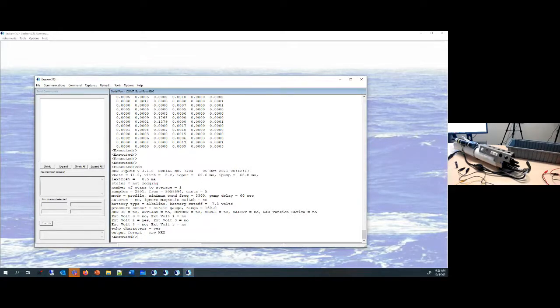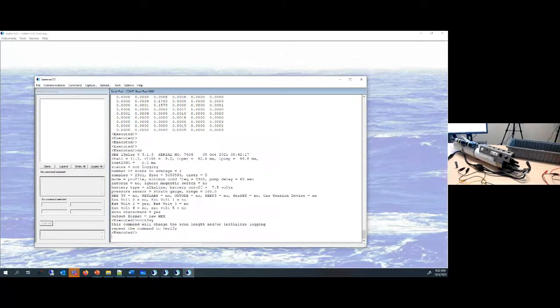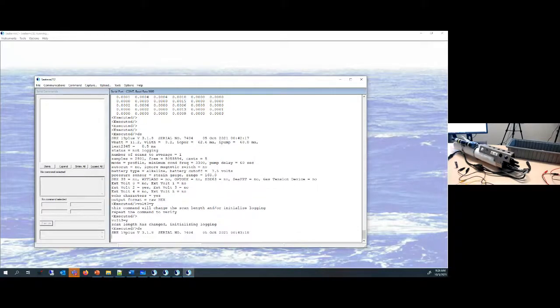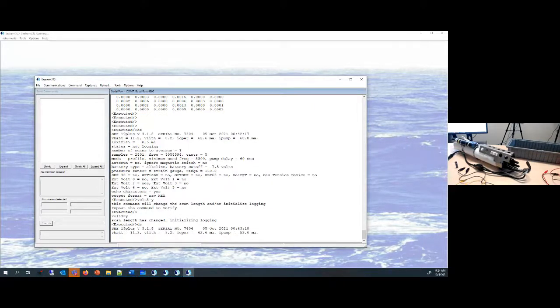So what you can do is fast forward the tape back to where you think your samples were and upload your data again. In this case, I'm going to send - we have 2,801 samples here - the volt3 equals yes command, which gives us a message: this command will change the scan length and or initialize logging. Initialize logging means reset the sample counter back to 0. So when I send DS, I can see that my sample count is now 0.